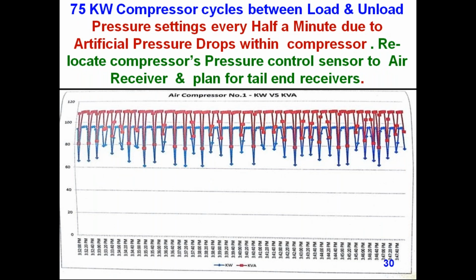A typical 100 HP compressor: because the pressure sensor is put in the compressor itself and the water separator is next to the compressor, it's almost choked. In an L&T industry where we did this, there was a batch of 6 compressors. We asked them to relocate the pressure control sensor from the compressor to the air receiver. Straight away, these fluctuations came down, and the savings were almost 10%. Instead of 5,500 units per day, their consumption on the compressor side came down to 5,000 units. Straight away, 10% energy savings just by relocating the pressure control sensor from the compressor to the receiver.